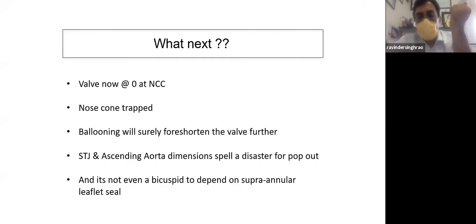But the only solution which comes to my mind is put the wire through the pigtail, upsize the sheath to a 12 French sheath, use a 23 millimeter balloon to dilate the lower inflow of the valve. The way to do it, you keep 50% of the valve anchored into the LVOT and not really towards the valve side, so the balloon is more towards the ventricular side. And definitely the other steps are basic - rapid pacing, and maintain a forward push on the balloon.